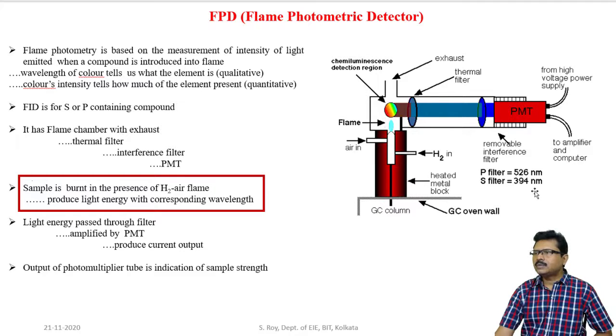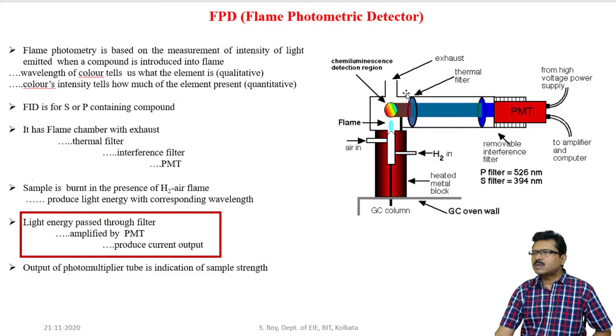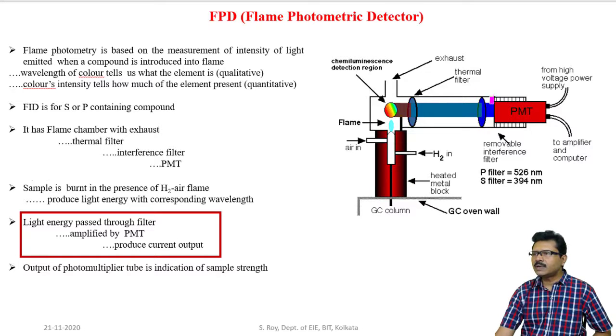For the case of sulfur, the light energy has a wavelength of 394 nanometers. For the case of phosphorus, the light energy has a wavelength of 526 nanometers. The light energy passes through a thermal filter and then through an interference filter. The thermal filter allows only visible and ultraviolet rays. Monochromators are normally used as the interference filter, which allows light energy with a single wavelength. When we want to detect whether there is phosphorus in the sample, a specific monochromator is used that allows only light energy with 526 nanometers.